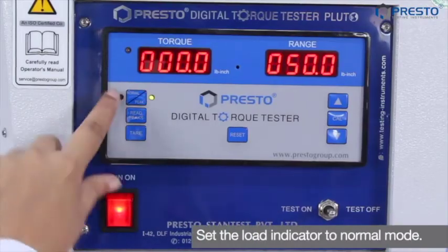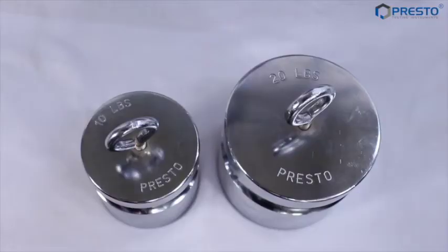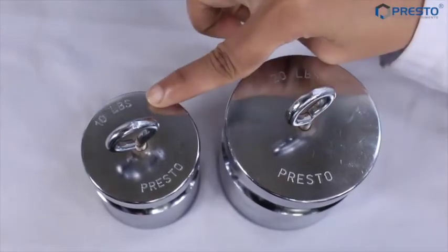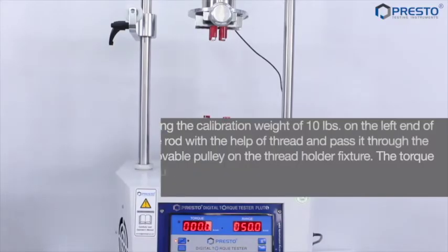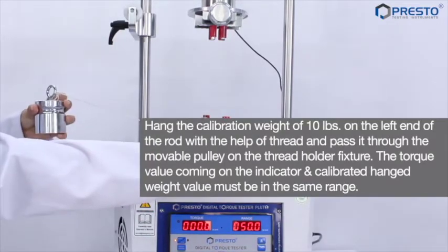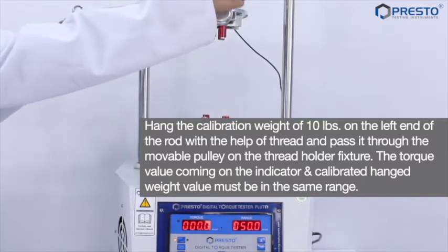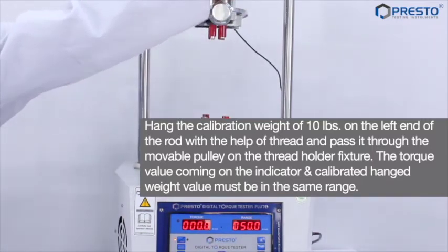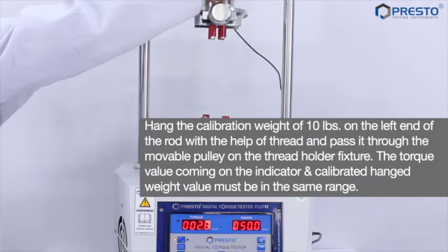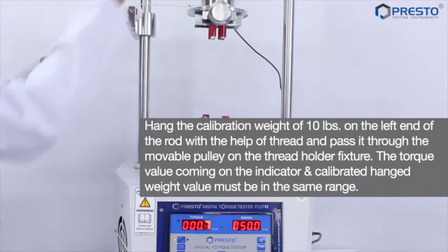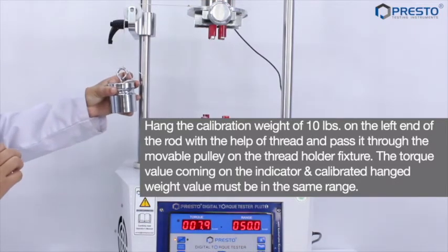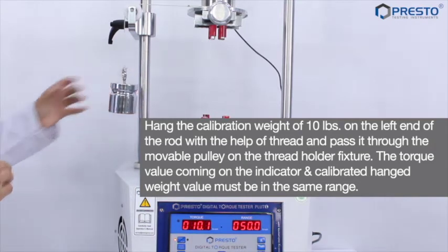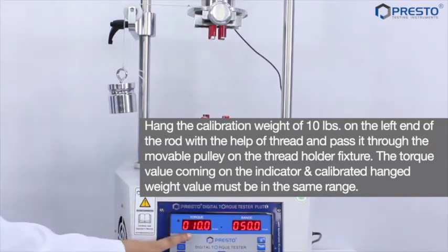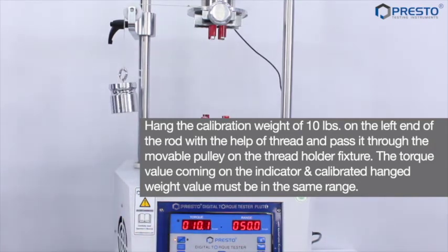Calibration procedure. Set the load indicator to normal mode. Hang the calibration weight of 10 lbs or 20 lbs on the left hand side of the rod with the help of thread and pass it through the movable pulley on the threaded holder fixture. The torque value coming on the indicator and calibrated hang weight value must be in the same range.